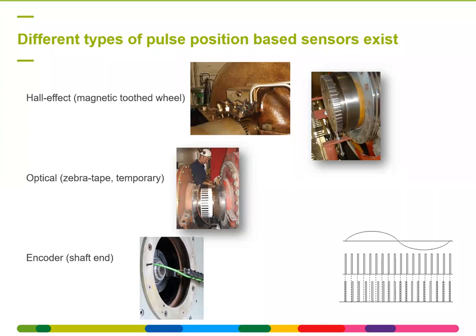There, instead of magnetic, it's optical. Here we recommend only to use this as a temporary measurement because it's optical, the zebra tape tends to get some dirt or some dust on it, and so the measurement then gets disturbed. So typically this is good for temporary measurement campaigns or to calibrate another sensor to validate the model, for instance. So these are also options. The third one is an encoder, which we have installed already in quite some power plants. These should be installed at the shaft end. And this is the advantage, it's a very high precision torsional vibration measurement device, which is as well optical. So your zebra tape, if you will, is within the encoder.